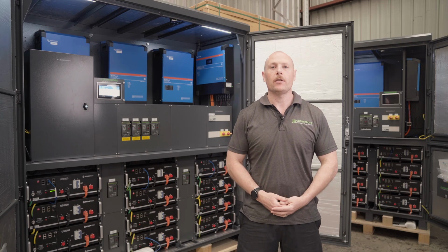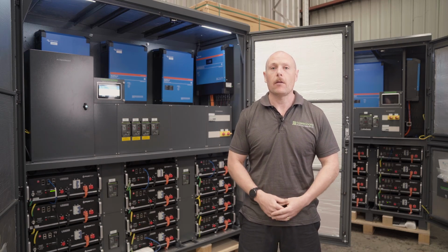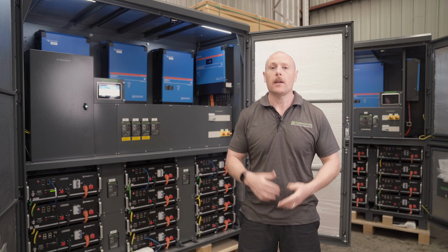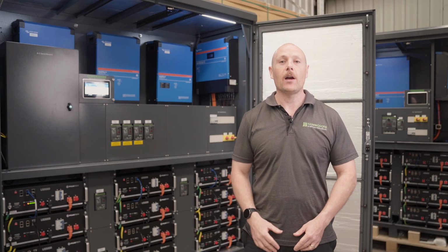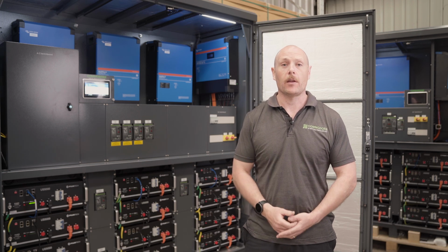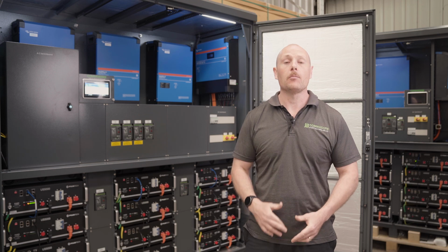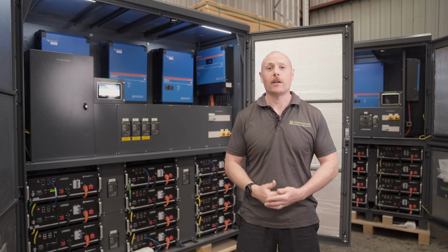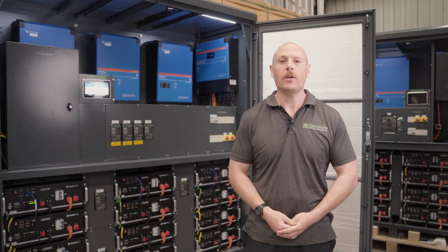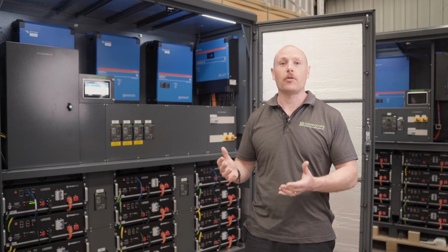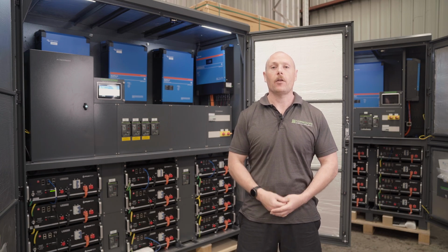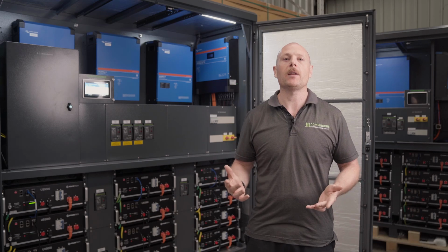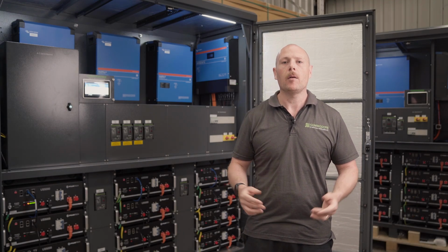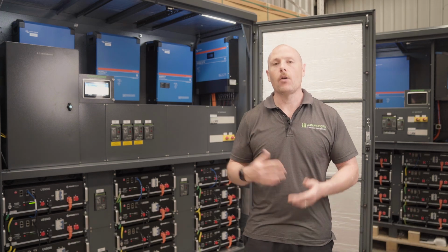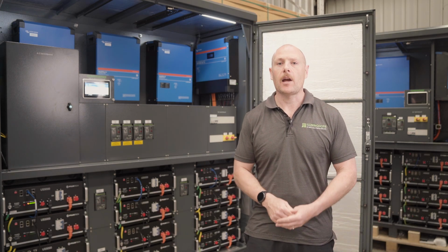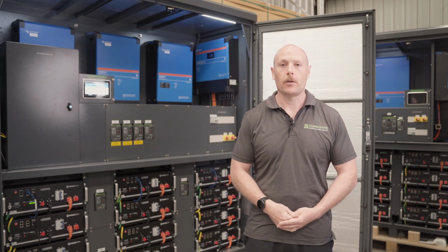The second configuration uses 2 separate cabinets. That's where we have one cabinet for the electrical equipment and the other cabinet is for the batteries. This is designed for larger commercial and industrial sites where there's a higher power demand, so that requires more hardware, hence the reason for a dedicated electrical cabinet. In this dual cabinet solution, we can fit up to 27 batteries into the battery cabinet, which is 135 kilowatt hours of battery storage. This type of setup will typically have 45 kVA of 3-phase power, but we can also go up to 60 kVA and 90 kVA when required, and we can DC couple up to 42 kilowatt of solar with this solution.